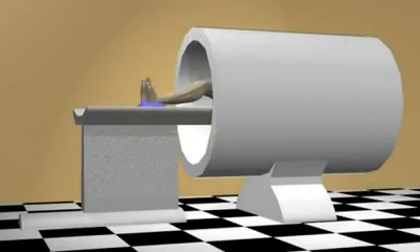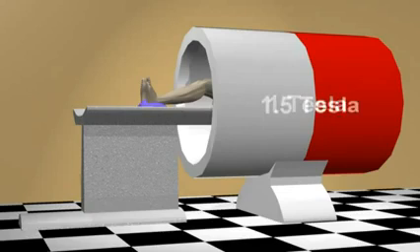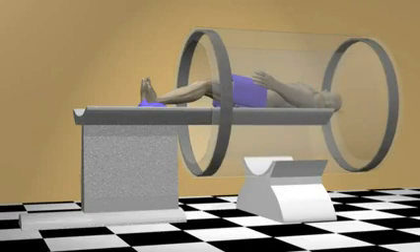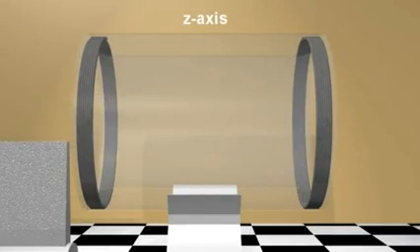When we first get into the MRI machine, a superconducting magnet creates a near homogeneous magnetic field from one side to the other that determines the strength of the MRI machine. Common systems are 1, 1.5, and 3 Tesla in strength. There are 3 sets of gradient magnets in the MRI used to localize locations in 3D space.